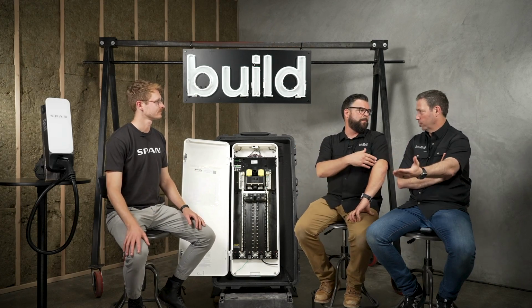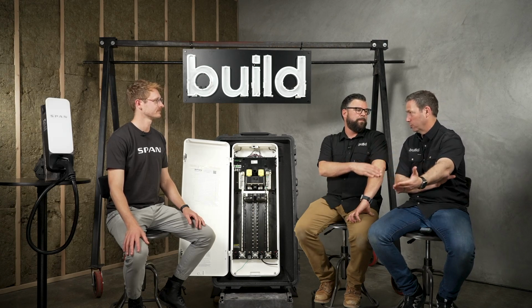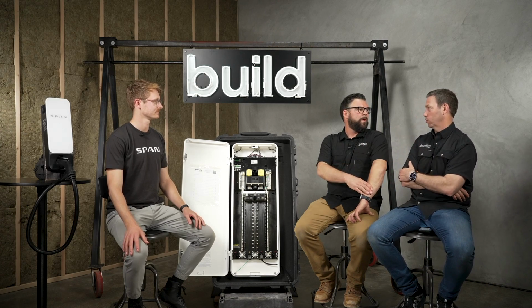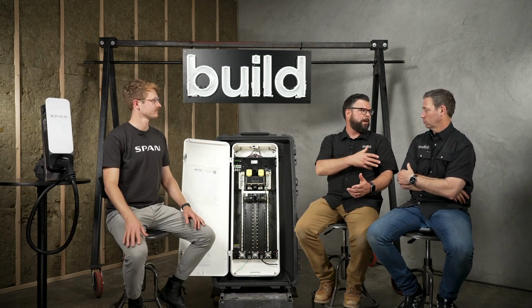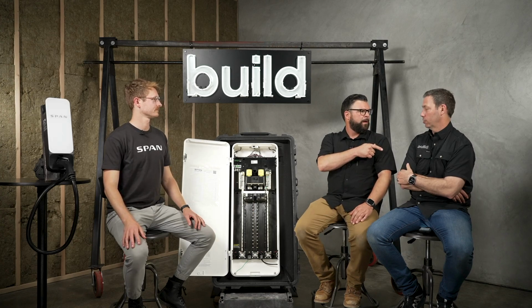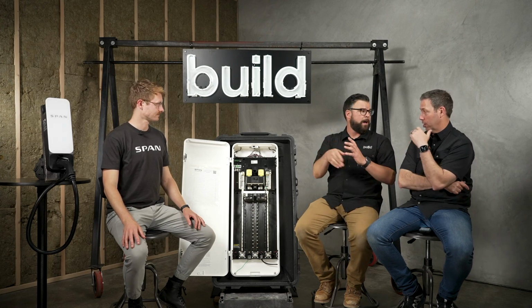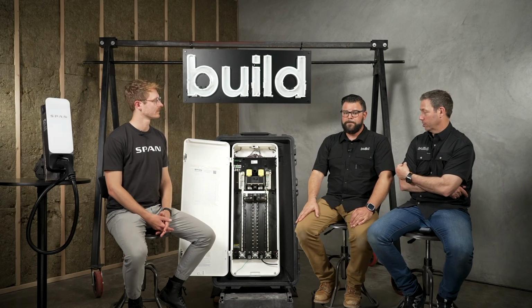If you've only got a 30 amp input from a generator, this is only going to have 30 amps to work with. I have an ATS, but I have a lot of customers with manual transfer switches, and when you have a manual transfer switch and a portable generator you deploy during an outage, you're already aware you're going to have to plug it in and pull the transfer switch. That's not the biggest deal in the world if people are trained and it's installed correctly, so I don't see an issue. Sure is nice to have that automatic though.